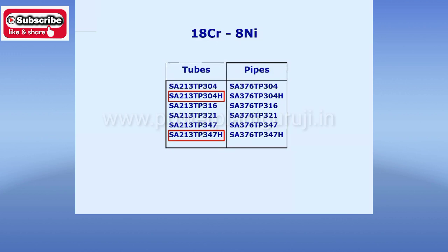The final few coils of the final superheater and the final reheater will be made of either SS304H or SS347H metallurgy. But the header will again be P91, because the header is not receiving heat — the final steam temperature will be in the range of 575–580 degrees centigrade, so there is no problem with using P91. Your main steam header will be of P91, but the final heating coils will be made of either 304H or 347H.